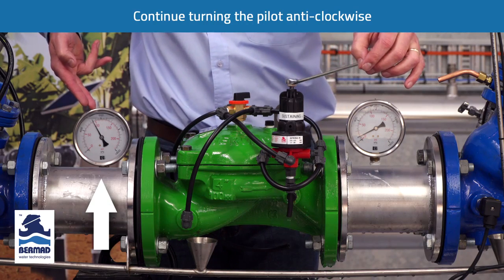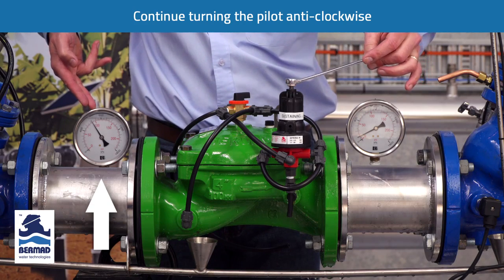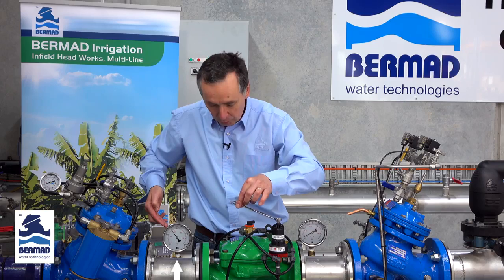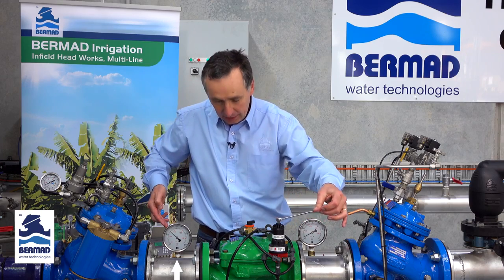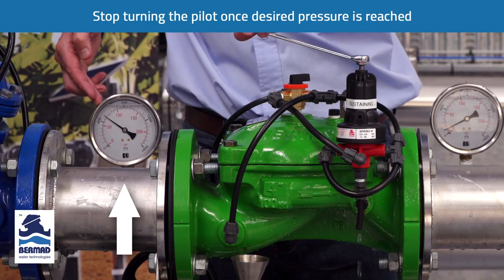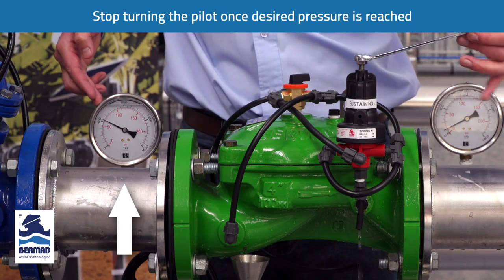We continue slowly turning the pilot anti-clockwise. We continually see water venting out through the bottom, and we do this until we achieve the desired pressure — in this instance, 400 kPa. We've now reached the target pressure of 400 kPa.